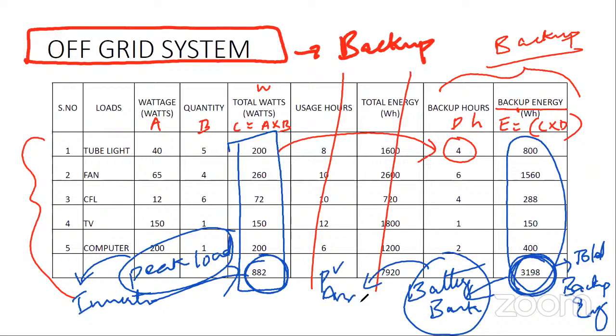So this is the approach of off-grid system design. First arrive at the peak load to understand the inverter capacity, calculate the backup energy to get the total backup energy for the battery bank design. Then based on the battery capacity, arrive at the PV array, because the PV array is brought into the picture to charge the battery bank completely during daytime. So the design of the PV array completely depends on the capacity of battery available.